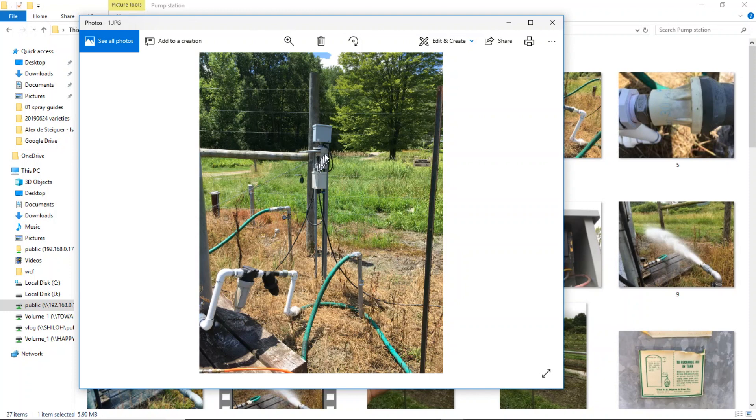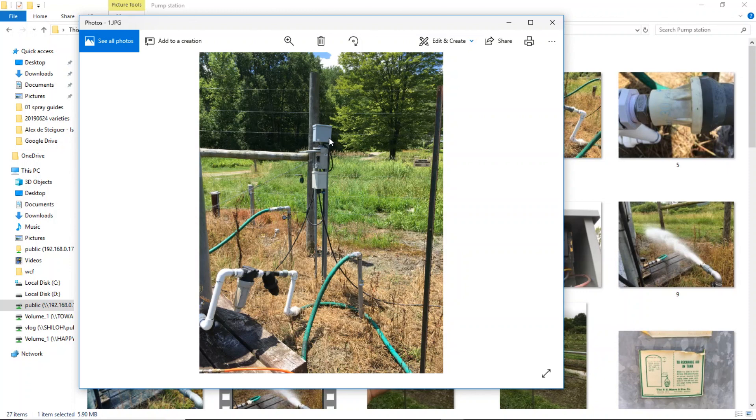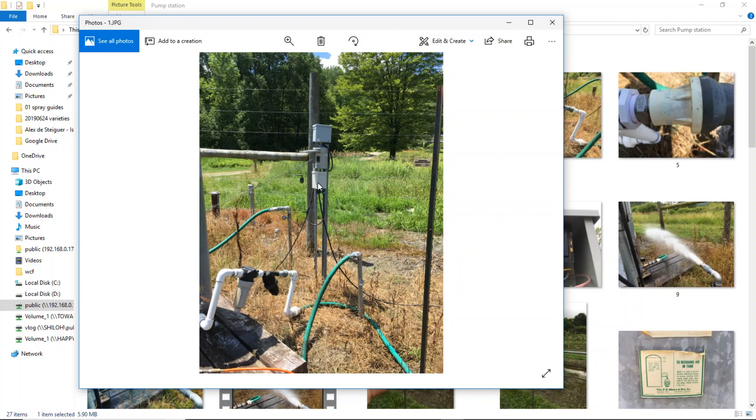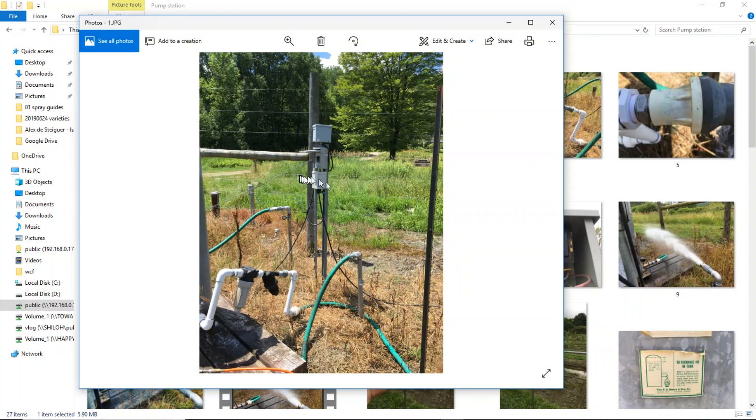Above that is a simple 240 volt breaker, a means to disconnect in National Electric Code jargon. Above that is the actual control box with metering and the control relay. The control relay has an umbilical here that goes down to the pressure switch on the volume tank, and that controls the power coming from the generator. When there's a call for water pressure, it reroutes the power to the submersible pump. It's actually pretty straightforward. Simple enough that I was able to draw a schematic on the inside of the cover to the control box.